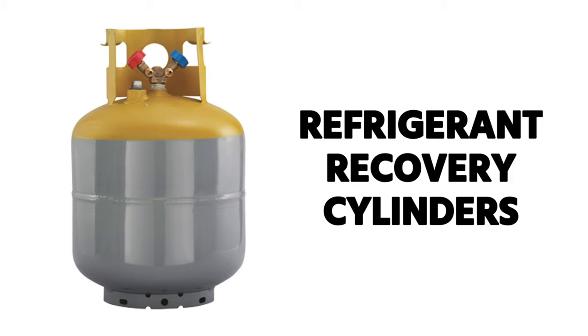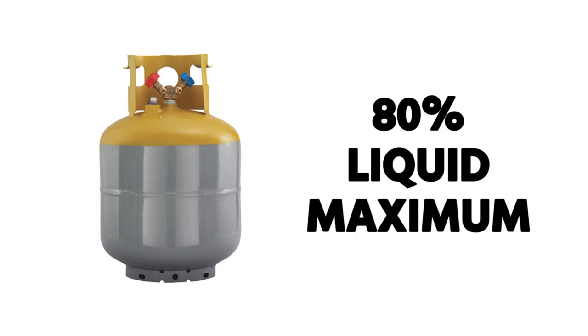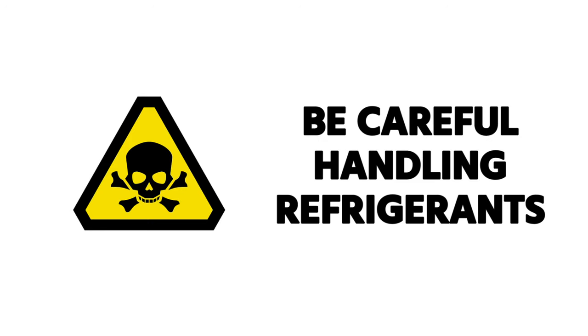Refrigerant recovery cylinders — and really refrigerant cylinders in general — are regulated by the DOT, the Department of Transportation, not by the EPA. Because these cylinders are transported on the road, the DOT regulates those tanks. Tanks used specifically for recovery have a gray body and a yellow top — that's the standard color code. You only fill those to 80% liquid maximum. Refrigerants that are heavier than air can fill a room from the bottom up, causing health problems as you breathe them in and displacing oxygen, including potentially causing death.